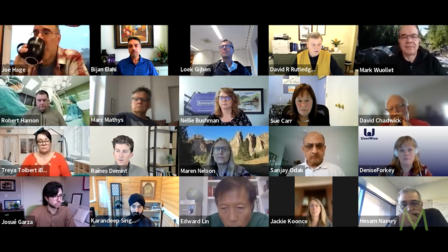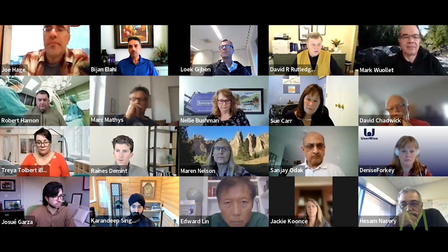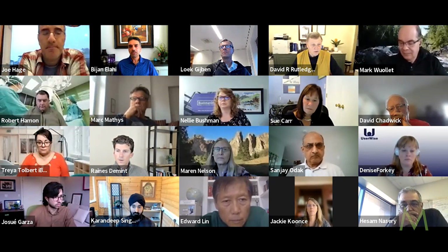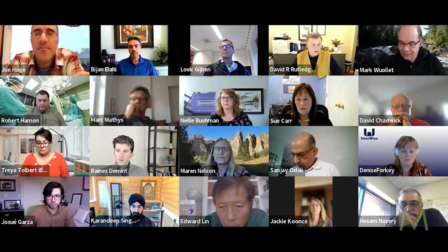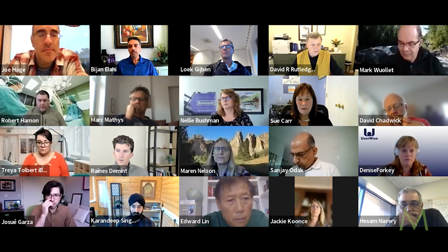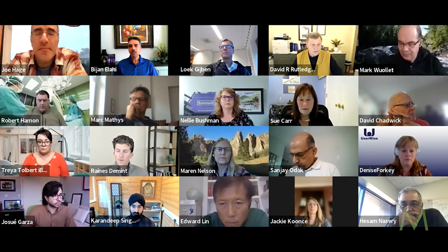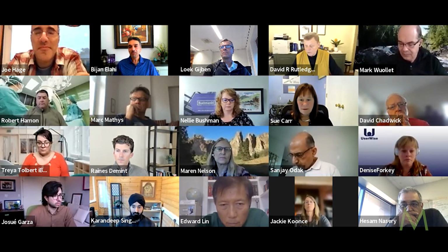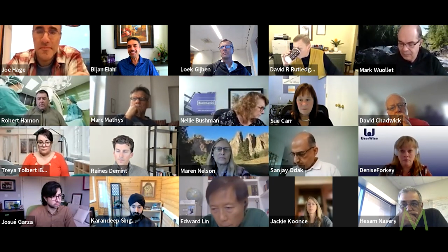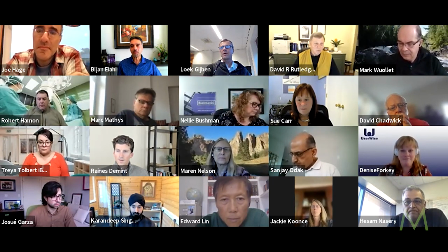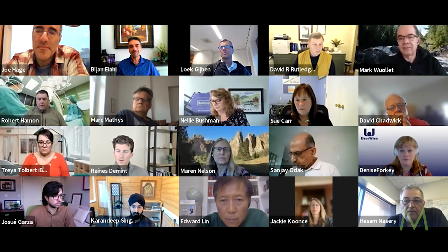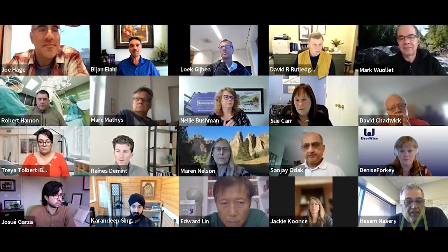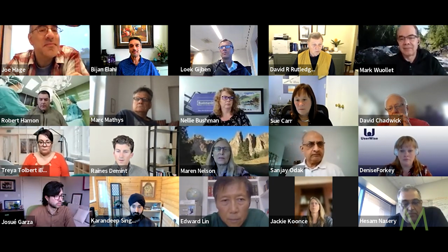The output of the risk management review is the risk management report. That's one of the actions that I mentioned. So that output produces the report or reviews the report. But notified bodies are just humans like the rest of us. So if you can persuade them by just giving them the risk management file and not the report, okay. But you're required to produce a report in general. I had not heard of anybody getting away without producing a report. Thank you.